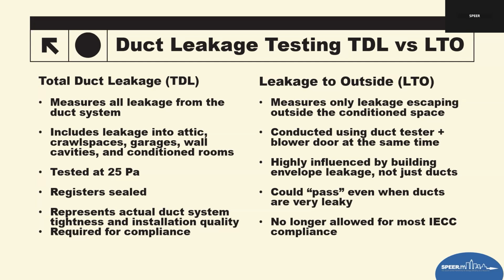The right side is leakage to outside, LTO. This is what we used to be able to do, and it's no longer allowed in the code itself. LTO only measures leakage that escapes to the outside of the conditioned space. This test requires both a duct tester and a blower door running simultaneously. Because the results depend heavily on how tight or how leaky the house is, LTO often hides real duct leakage issues.